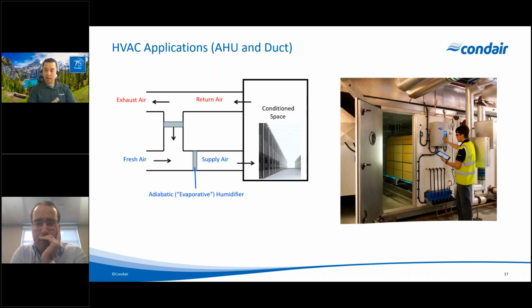So, just a high-level overview. For HVAC applications, we are installing the humidifier or the adiabatic system directly in the supply air system before it gets to the conditioned space. Traditionally, it would go inside of an air handler or in some cases inside of the ductwork as well. But generally, these are being installed inside of an air handler that is supplying a specific zone or potentially multiple zones as well.